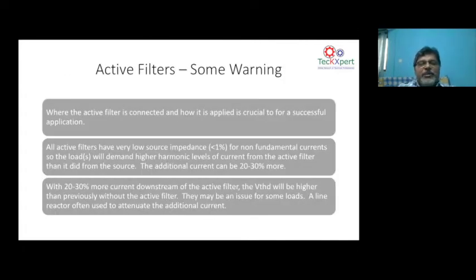And now some warnings, these are all the last slides. Where and how the active harmonic filter is applied is very important for a successful application. You have to be very careful in terms of how you select this active harmonic filter. It should be done by careful study. You should not just blindly buy an active harmonic filter and just install it.